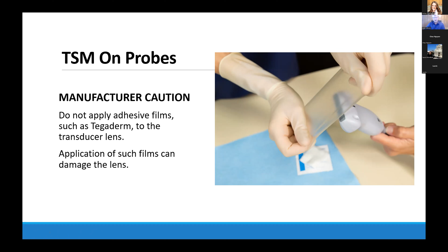So when you look at this, this probe is hard plastic, but this foot is where the lens is. This is not hard plastic. And pulling these adhesive dressings off of this foot will over time degrade the foot, damage it, potentially crack. It's going to void your warranty, and then you're going to have a new probe. May not happen the one time that you use it, but if this is your standardization process, and you do a lot of them, you're going to risk damaging the probe.